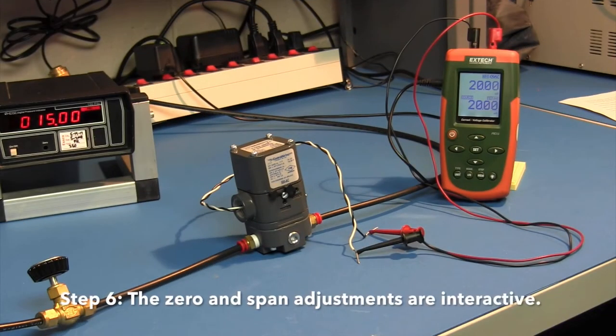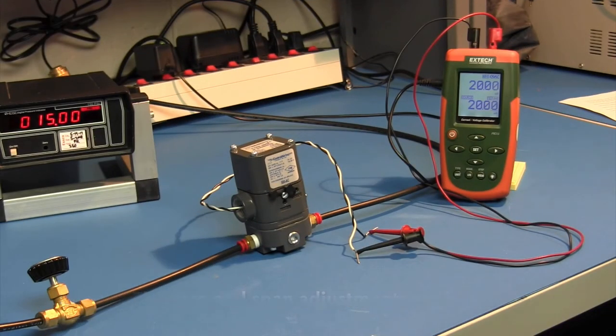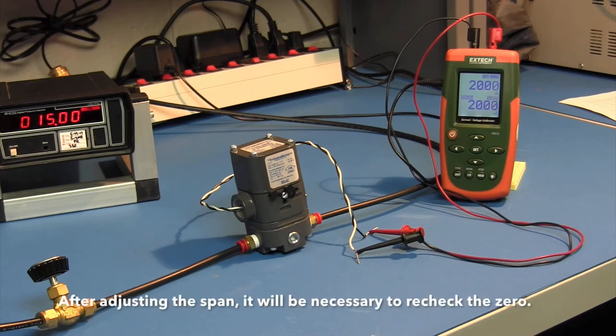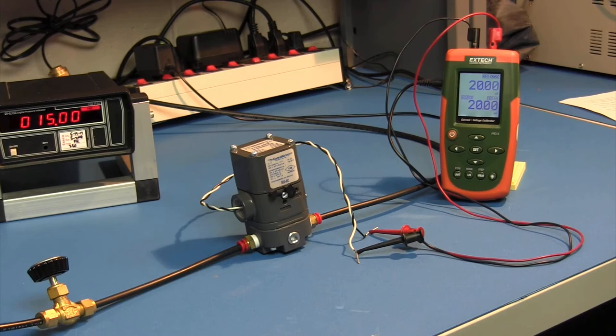Step 6. The zero and span adjustments are interactive. After adjusting the span, it will be necessary to recheck the zero. It may take two or three iterations to get the correct setting.